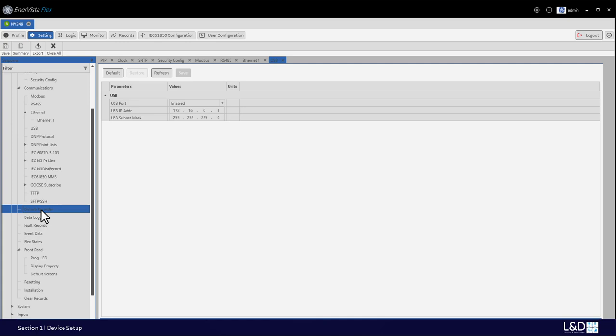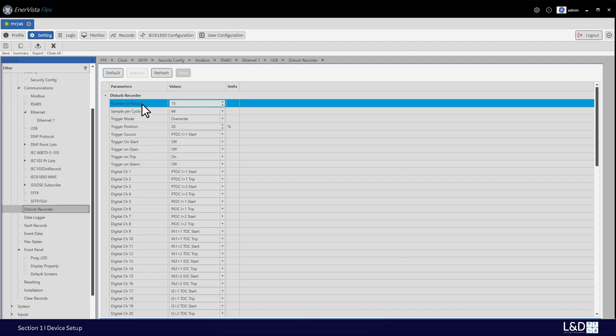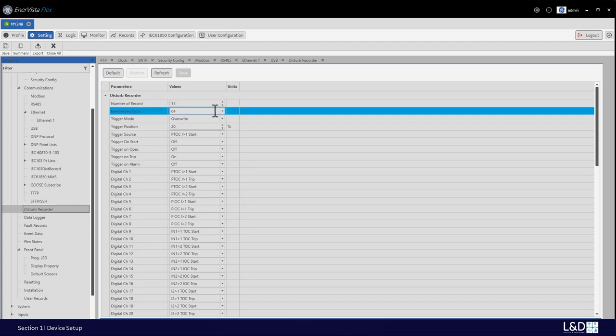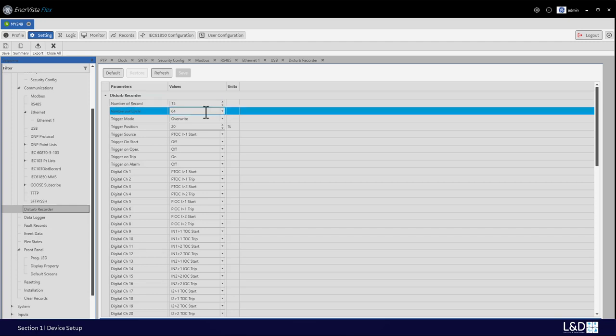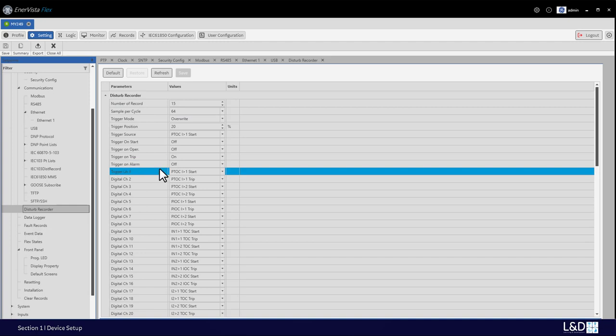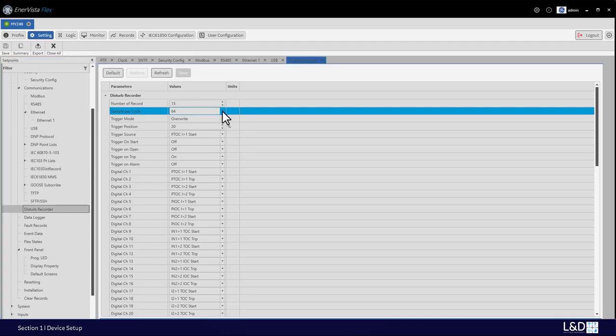Now let's open the disturbance recorder settings. As introduced in module 102, here are the settings for how waveforms are captured. For the number of records, we can choose a maximum of up to 16 records. The length of each record is based on the number of records, the sample rate, and the number of selected analog and digital channels. There is a fixed amount of data storage for the disturbance recorder. The more data captured, the fewer cycles captured per record. The sample rate can be set up to a maximum of 128 samples per cycle.